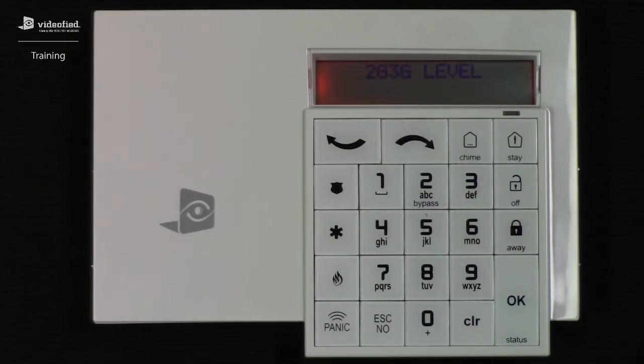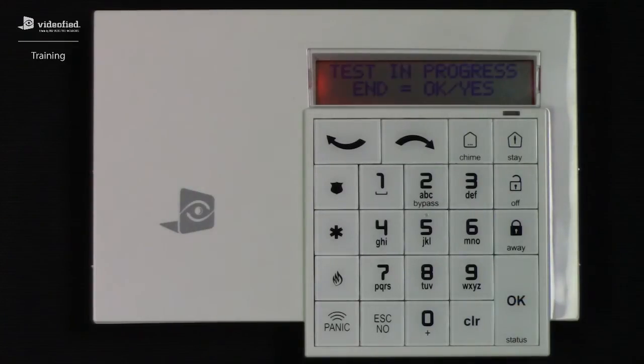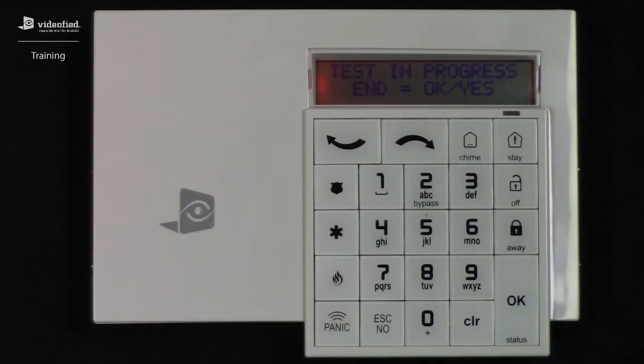Next, left arrow to the 2G3G level option. The 2G3G level will test cellular signal and will display a result as a number out of 5, followed by the cellular network to which it is connected. Once this test has been initiated, keep in mind that it can take approximately 30 seconds up to 2 minutes before it will return its final result.